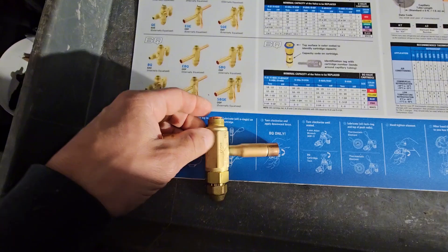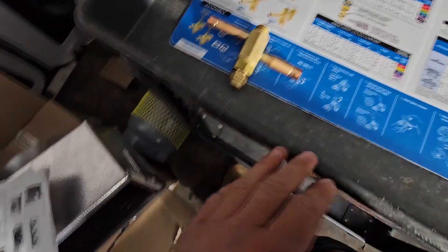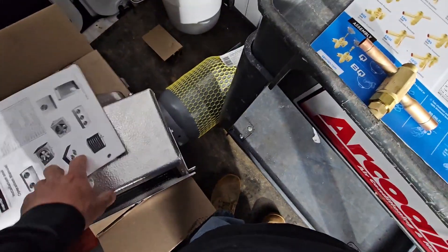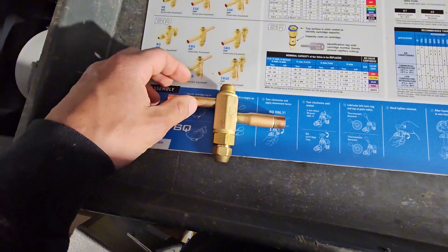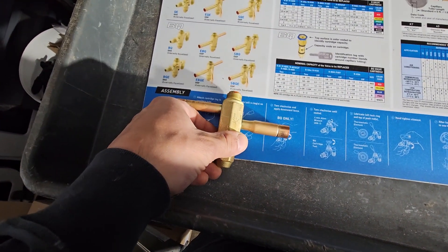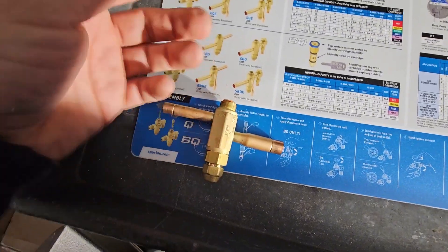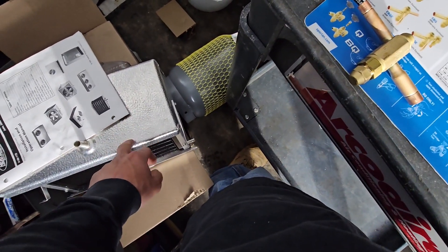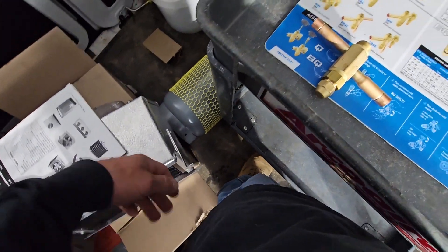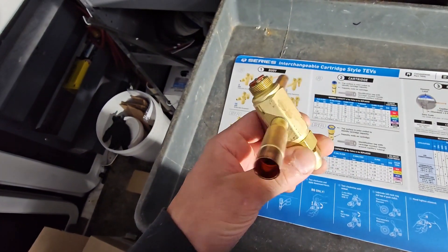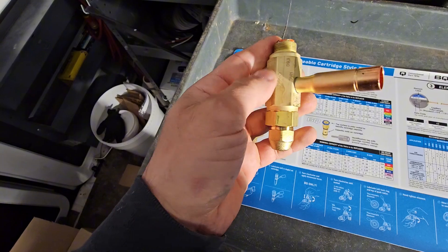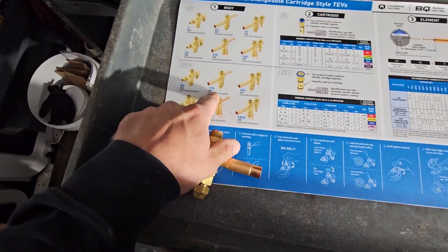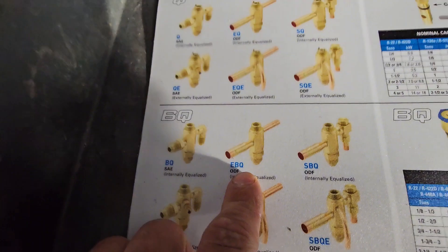So what I'm doing is I've chosen, I have my orifice already selected. So basically I'm going internally equalized, why? Because there's no distributor on this, so there's no nozzle. So basically you've got to go internally equalized when you have no distributor. And typically small evaporators like this will be internally equalized, which is basically two ports. You don't have that little port on the side. So I've selected an EBQ, so that's number one.